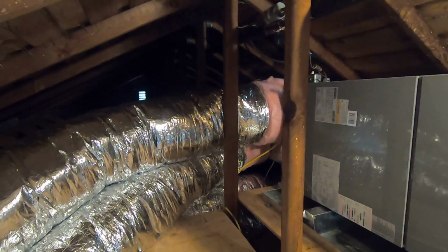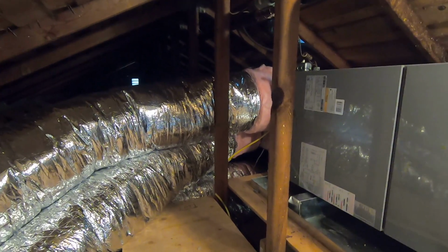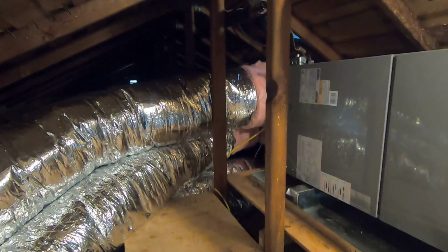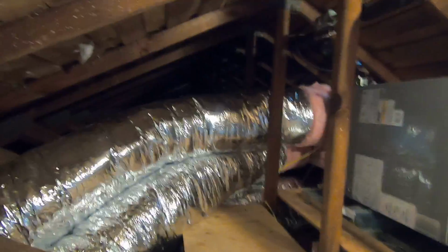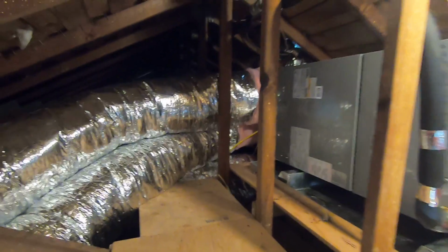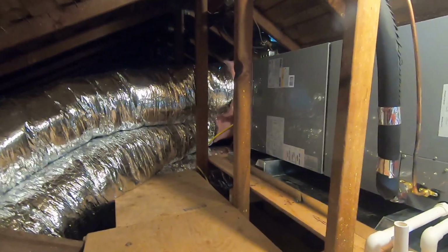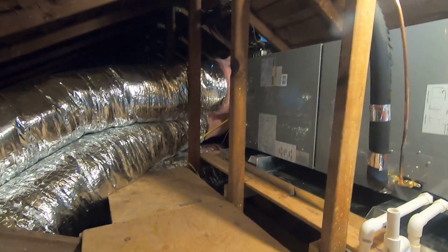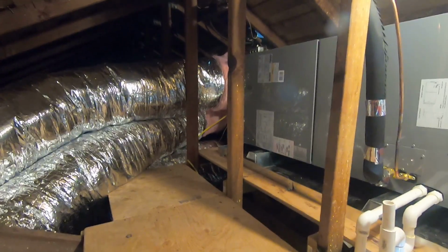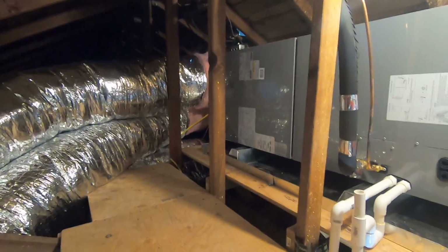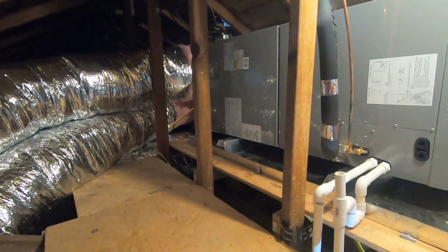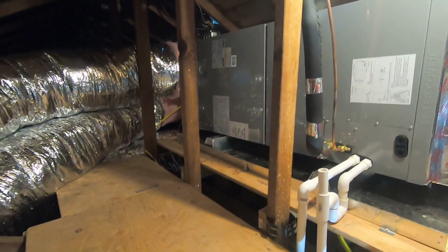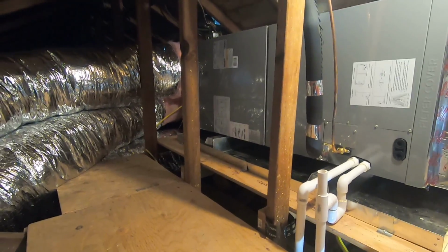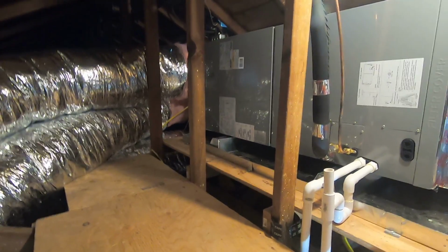Then on the supply side, we did all new ducts on that side. These are all R8 flex ducts, so they're very well insulated. They are code in this area in Southern California, so we ran all new ducts. We even cut some of the holes bigger in the rooms. The old ducts that were going there were very small, the grills were very small, and the boxes were very small.